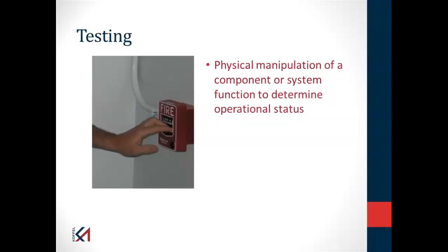We do not do testing. We're not really set up to do testing. Testing often requires special equipment. If I were to test your sprinkler system and a coupling failed, I would have no choice but to turn that system off and leave you with an impaired sprinkler system. A contractor potentially can repair your system and get it back into proper operating condition. I would have to tell you to call a contractor to do that repair. But I'm actually testing, flowing water through a fire pump or something along that line.